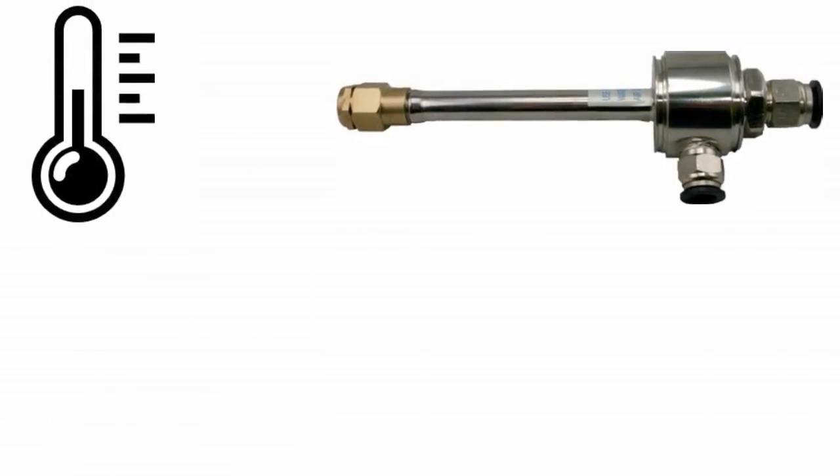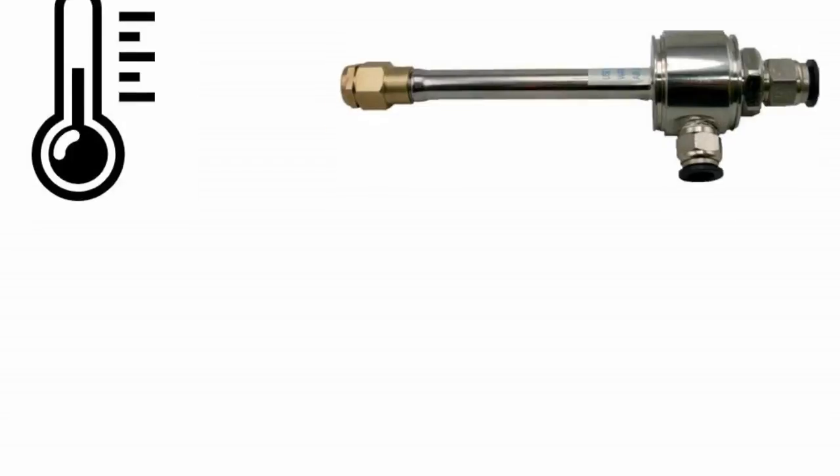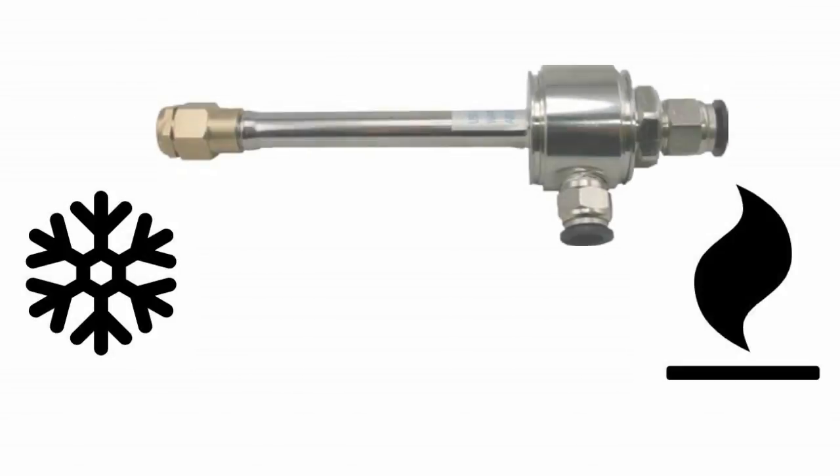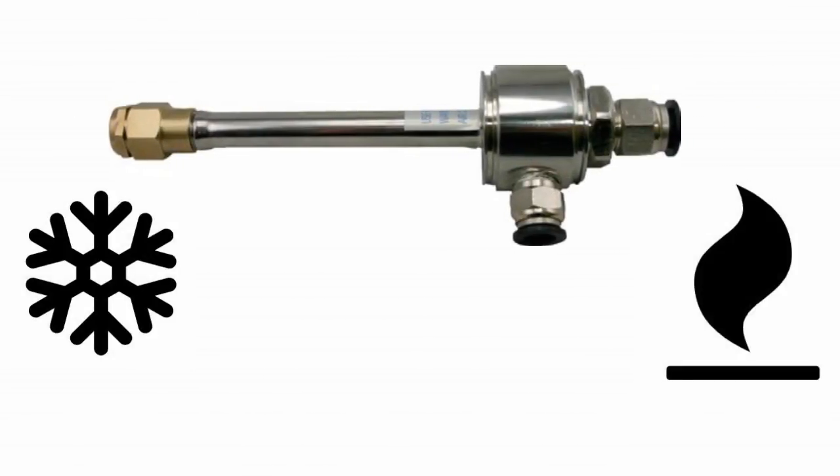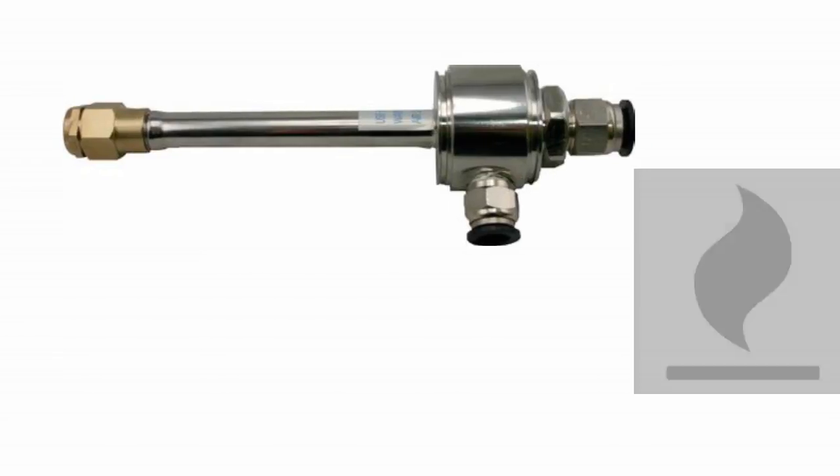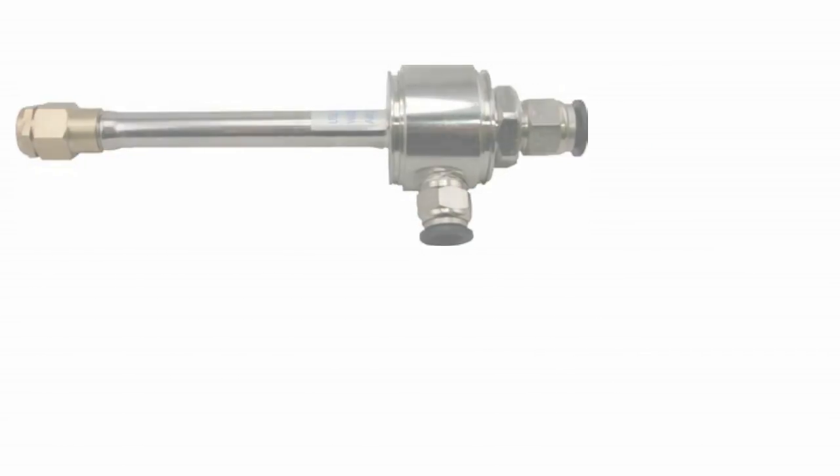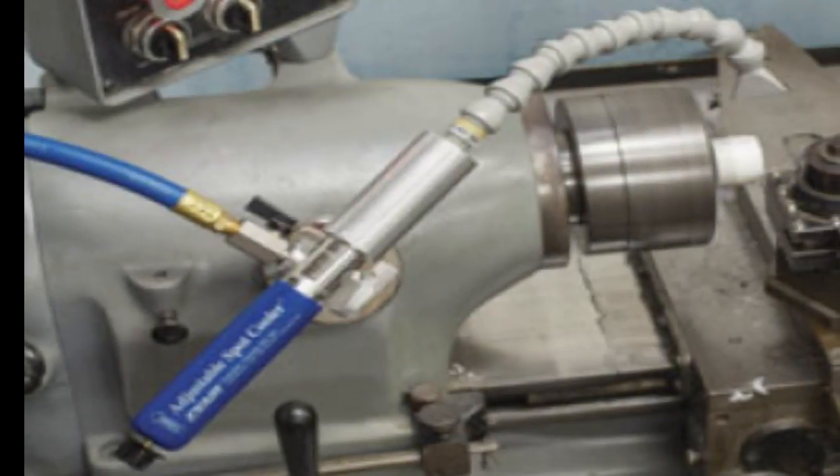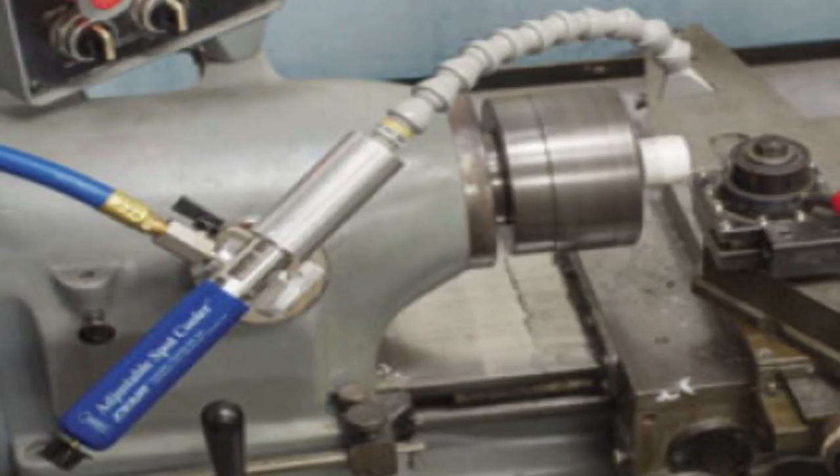At the cold end, you can achieve air stream temperatures of minus 50 degrees centigrade and at the other end, you can get as high temperature as 200 degrees centigrade. The most common use of vortex tube is spot cooling where compressed air is available.